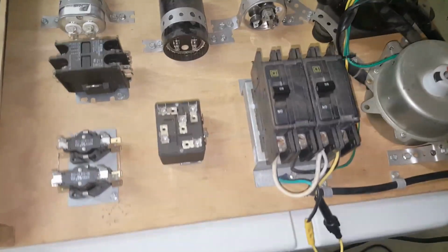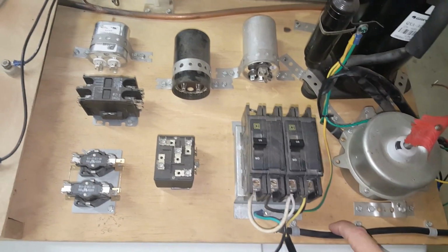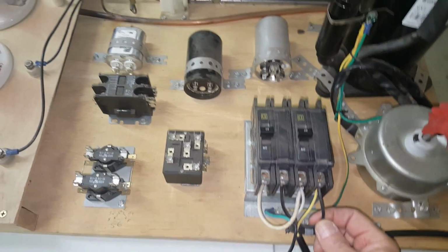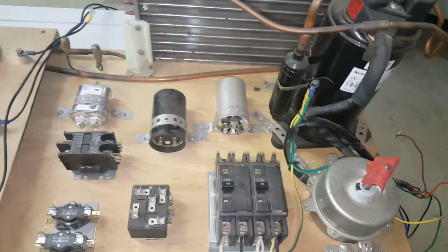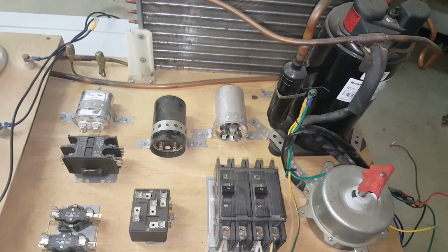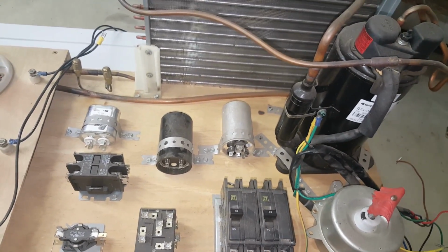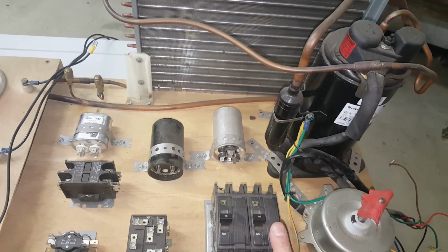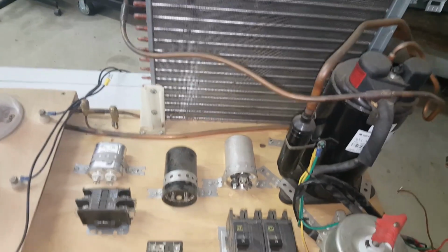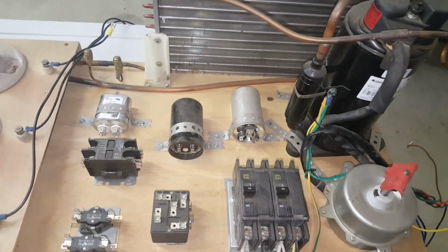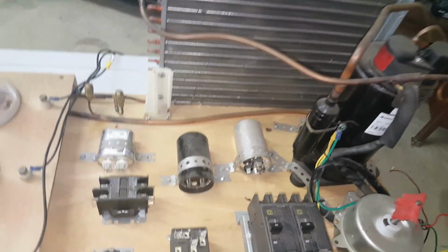We have two double pole 60 amp breakers right here at our power source, and we have our black wire coming in from the power, going through our fuse protection just for safety reasons on this simulator. We're coming into line 1 on this breaker, and line 1 jumps over here and also feeds this breaker. And then you have line 2 coming into this side of this disconnect breaker and also feeding the other side of line 2 here.